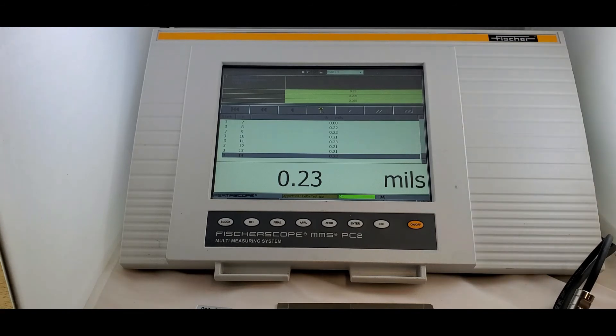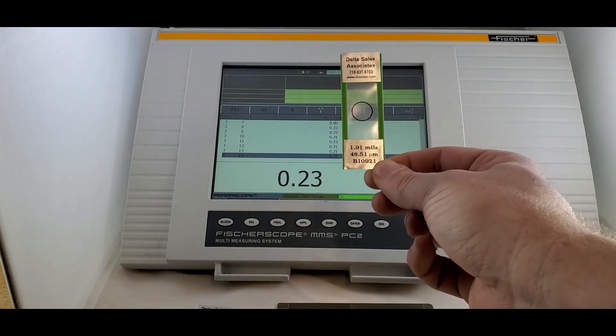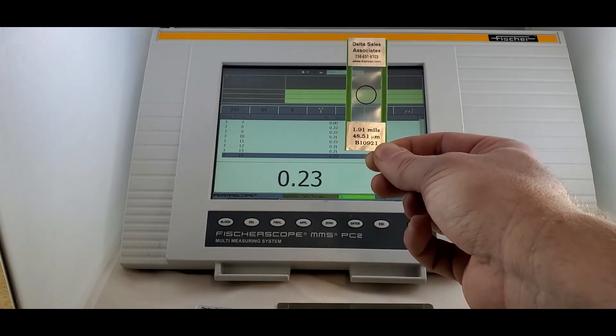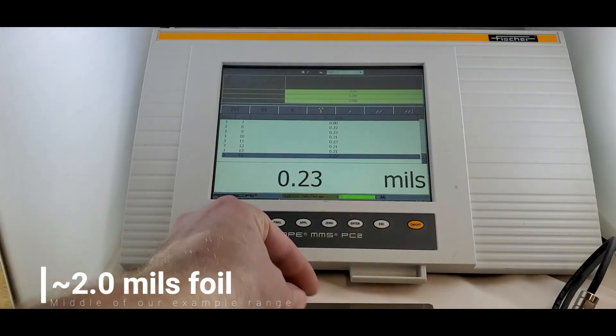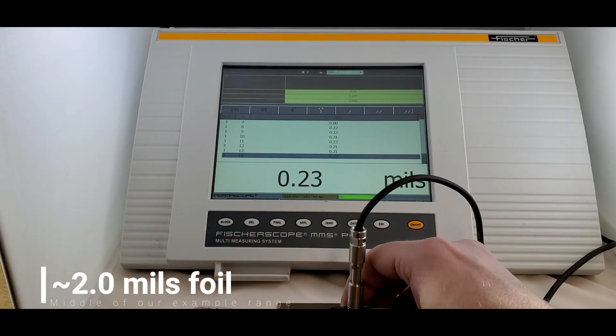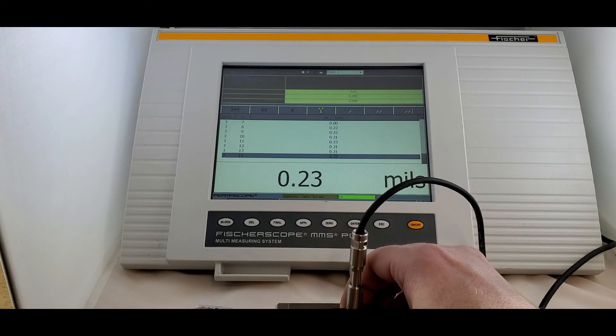So now in theory, we are calibrated, but we want to make sure. And now this is a very good way to do a daily verification. We are going to take a foil that is now right in the middle of our range. So I'm just going to take a couple of measurements on this to make sure that our calibration was correct.